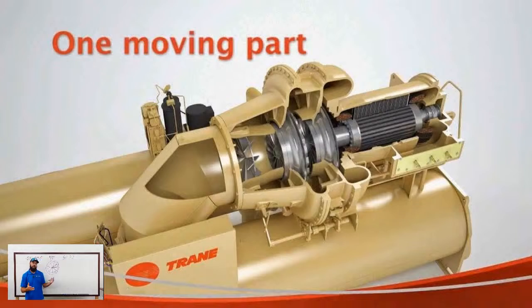Now, granted, this is all saying that nothing inside the compressor has come apart and we've got vanes doing things they're not supposed to. But barring that, and everything inside is working properly, those actuators do fail, or the linkages sometimes bind up. You know, things happen.